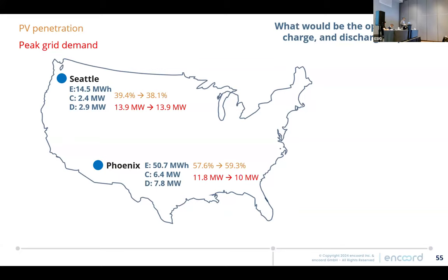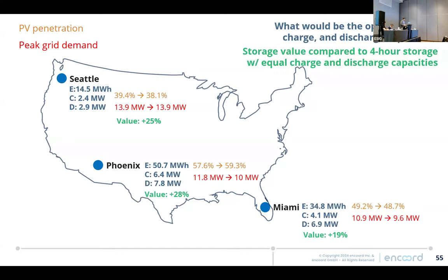And on top of that, we have an increase in PV penetration and a further significant decrease in peak grid demand. If we look at Miami, we see very similar behavior, but to a lesser extent. So we looked at what is the value compared to the four-hour storage. What is the value of this decoupling? The value of storage increases by 25, 28, and 19% respectively, purely from this decoupling.